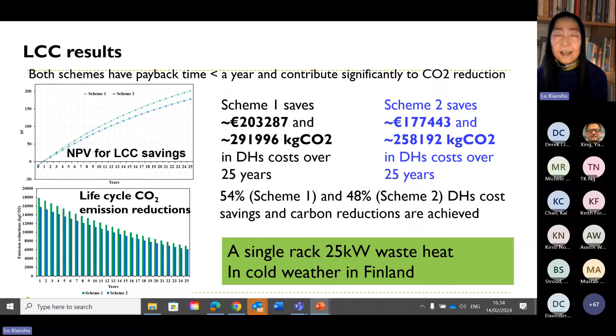Discussion and conclusions. This is quite interesting, because initially we thought that full, complete recovery of waste heat from the data center could be achieved if the building heating demand exceeded the waste heat. But the results show a very different reality, because you remember the graph I showed earlier, Scheme 2 is represented by this blue line, and in Scheme 2 the waste heat recovery drops as outdoor temperature drops, meaning that building heating demand increases because the temperature drops. So this is not true. What we thought in the beginning was not true.